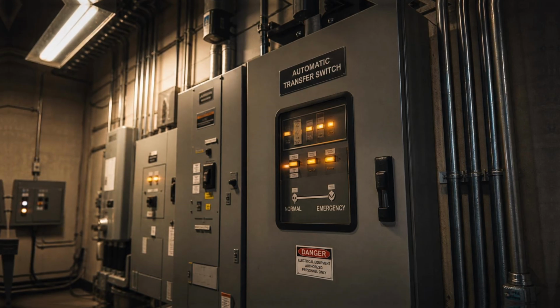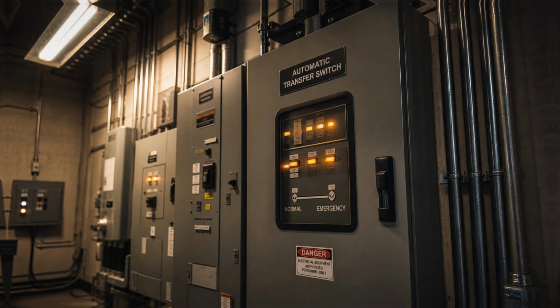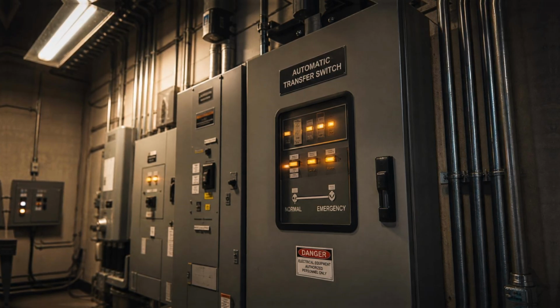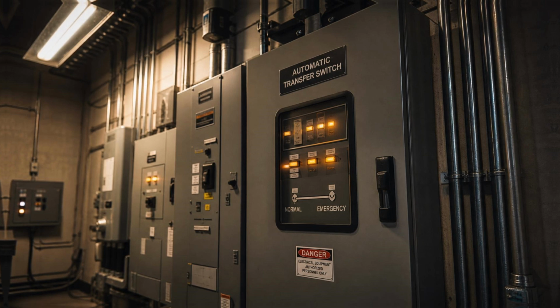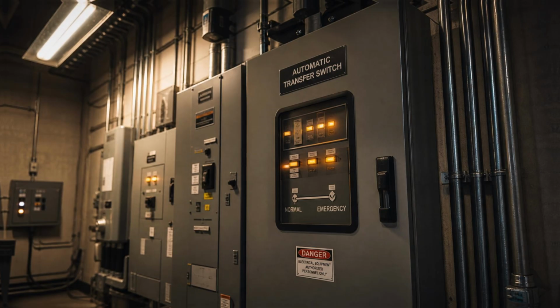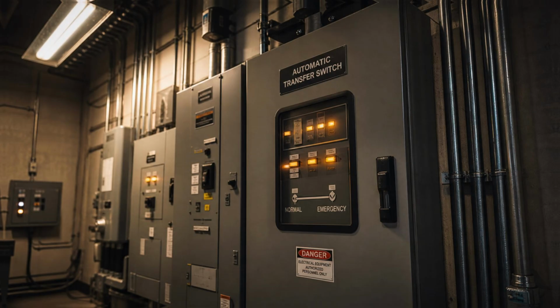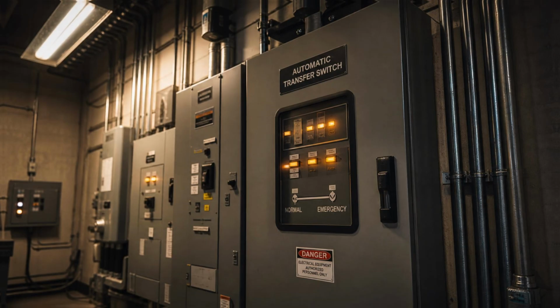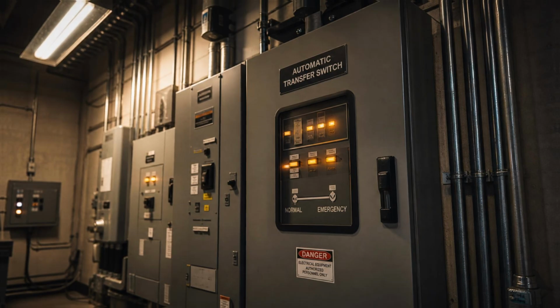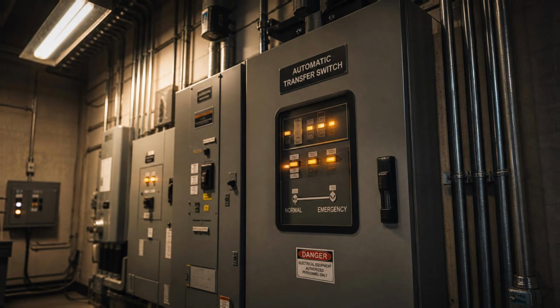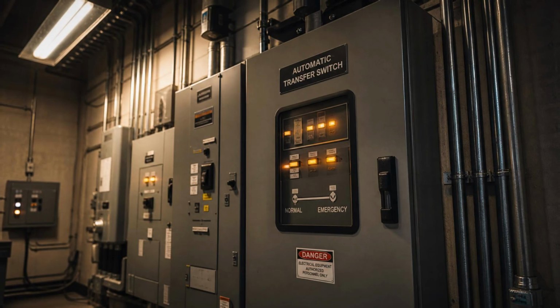Time that a hospital patient on a ventilator does not have. Time that a smoke exhaust system controlling the spread of fire in a stairwell cannot afford to wait. The automatic transfer switch removes all of that time from the equation. The response begins not when someone notices, but when the monitoring system detects, which is to say, it begins almost immediately. The sequence itself unfolds in a particular way, and there is something almost meditative in following it step by step. The monitoring system, which we followed so carefully in the previous chapter, watching voltage and frequency and phase with its patient, continuous attention, has determined that the utility source is no longer acceptable. The signal has been sent, and now the automatic transfer switch is involved.